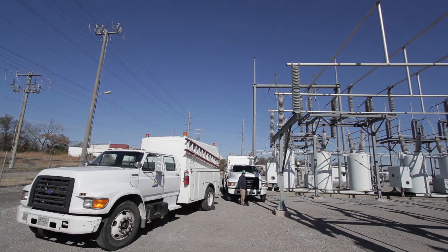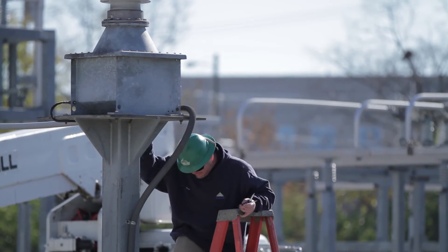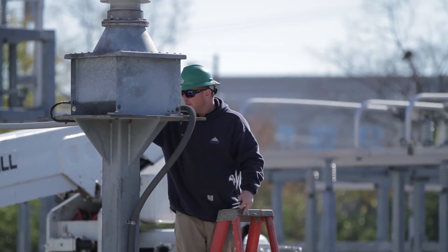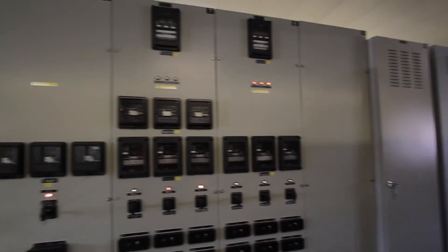With the analog controllers, we're able to intercept the voltage coming from what they call the potential transformer that feeds information to that tap changer controller module and adjust it to fool the transformer into thinking the voltage is actually too high.